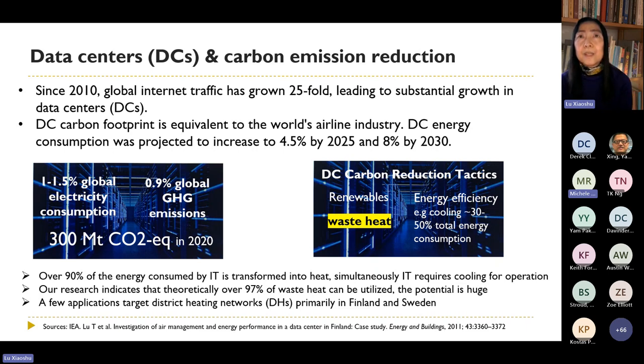due to the nature of IT system, because over 90% of energy consumed by IT is converted into heat. And at the same time, IT requires cooling for function. One of our studies indicates that in theory, over 97% of waste heat can be utilized. The potential is huge. However, practical applications are limited due to various challenges. For example, the waste heat is low grade heat that is not easily applied to traditional thermodynamic processes.